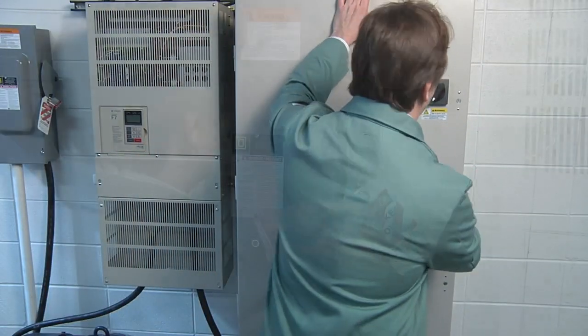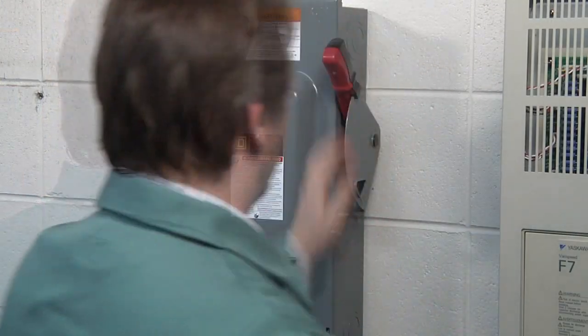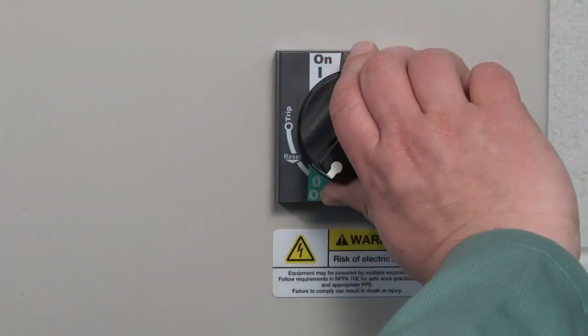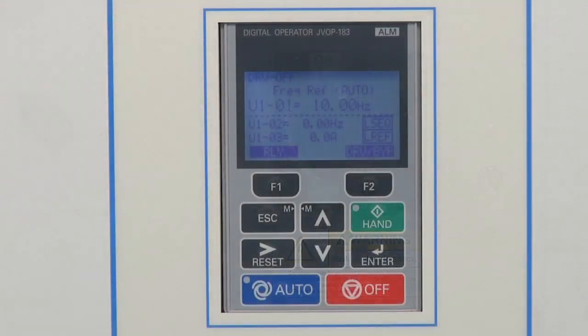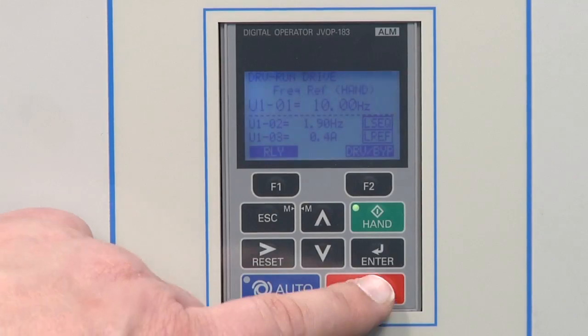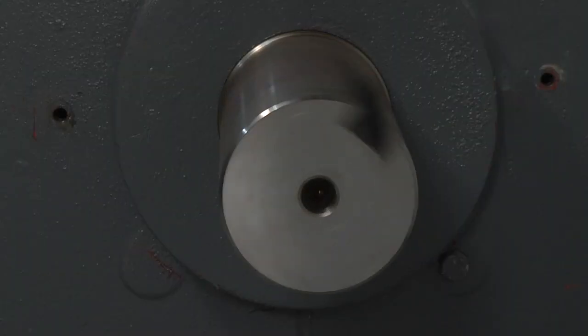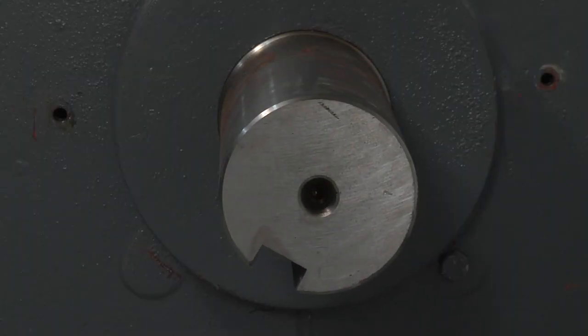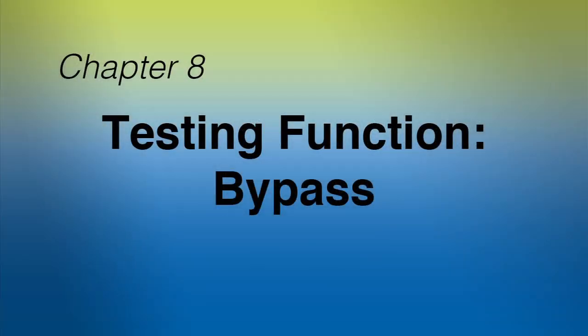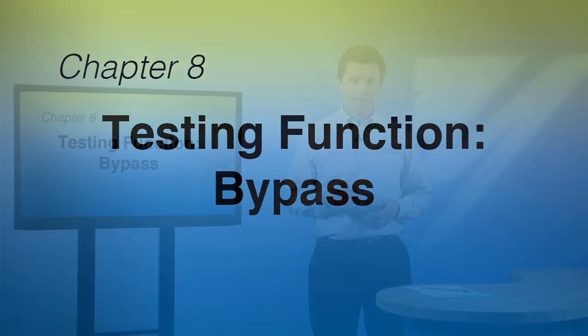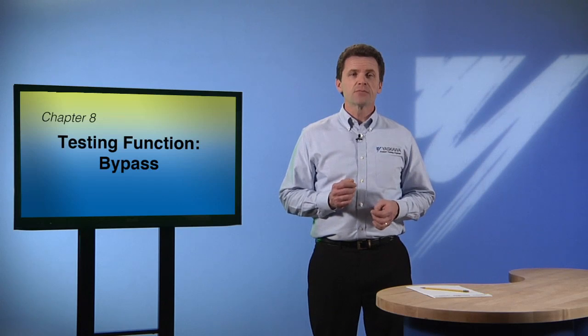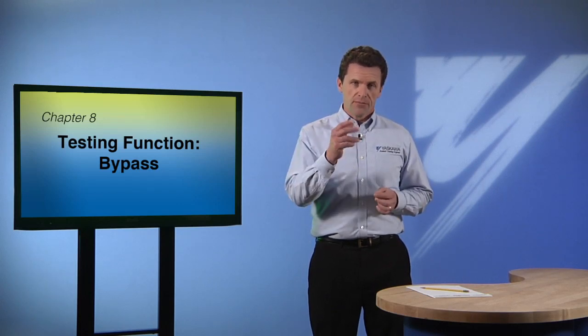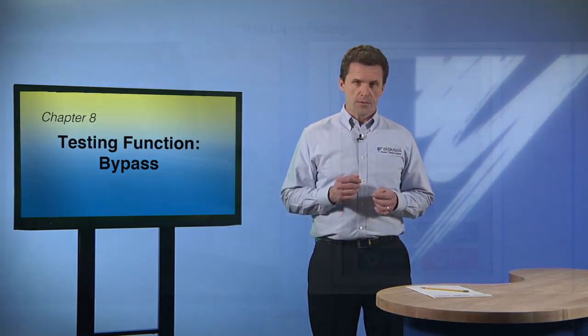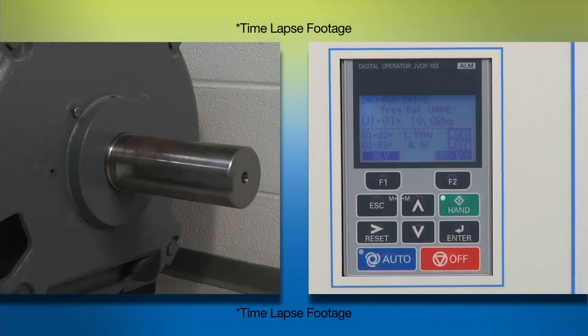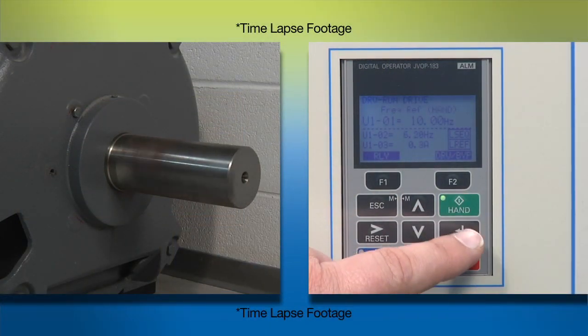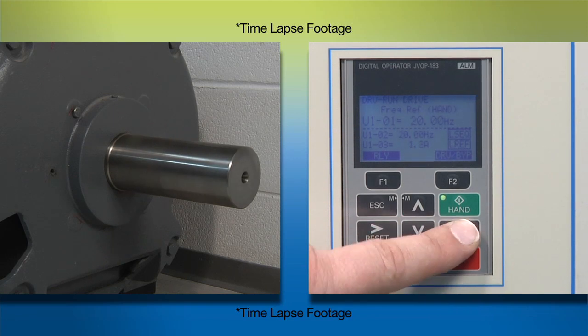After the leads are switched, close the door and power up the bypass. Perform the bumping procedure once again. Hand, then off. When you check now, the motor should be spinning in the proper direction. Now we're ready to safely test the motor all the way up to 60 Hz, the level it will operate at when it's in bypass mode. Start in drive mode and use the keypad to increase the speed by increments of 10 until we achieve a full 60 Hz.